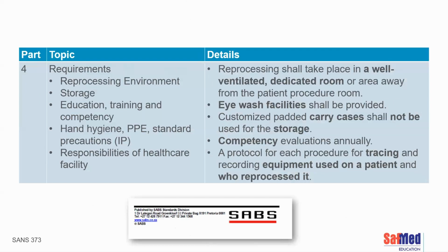Touching on a few points now, in Part 4, the reprocessing environment talks about having a dedicated room, and that reprocessing should take place in a well-ventilated, dedicated room or an area away from the patient's procedure room. It also describes the flow and design of that room, the temperature, the humidity, those kinds of aspects. It talks about the fact that we need wash facilities in that area - if anybody should get any splashes in the eye, that we can, from an occupational health and safety perspective, have a facility available for that.